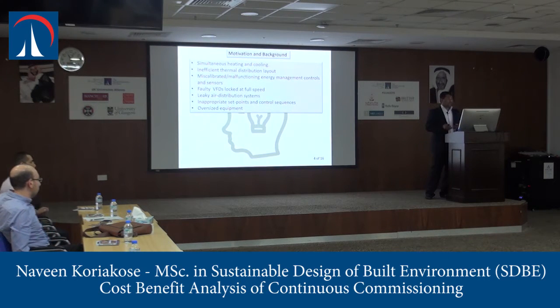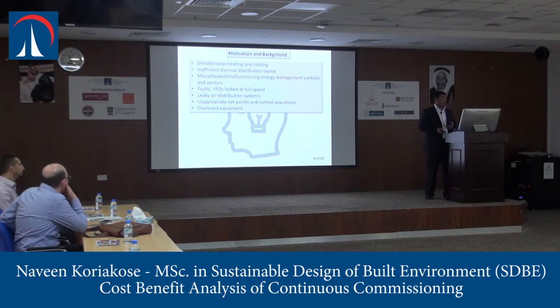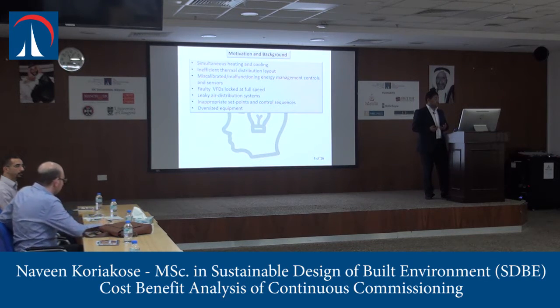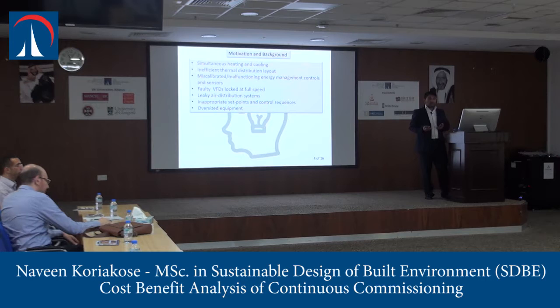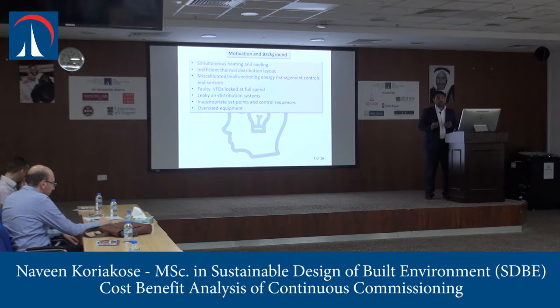Generally, these are the outcomes from commissioning: simultaneous heating and cooling can be identified, inefficient thermal or air conditioning distribution can be identified, calibration issues on sensors can be identified, and oversized equipment can be identified.